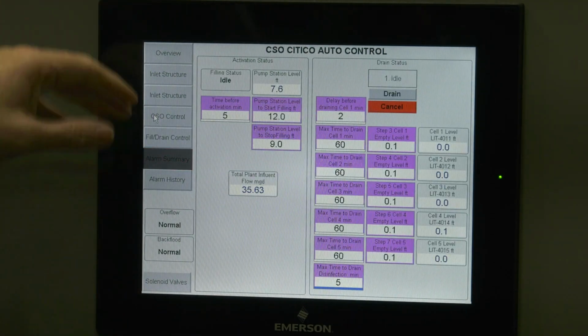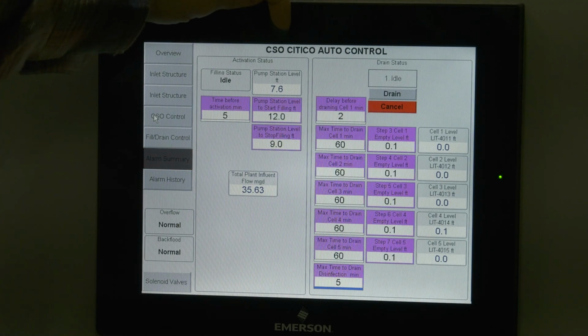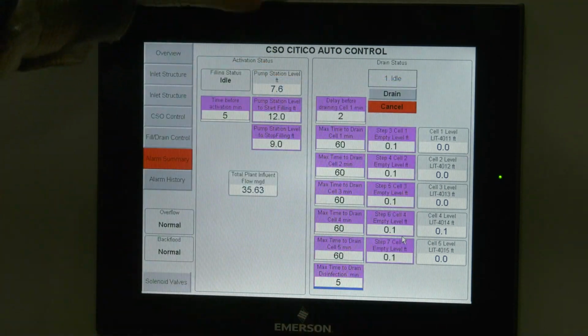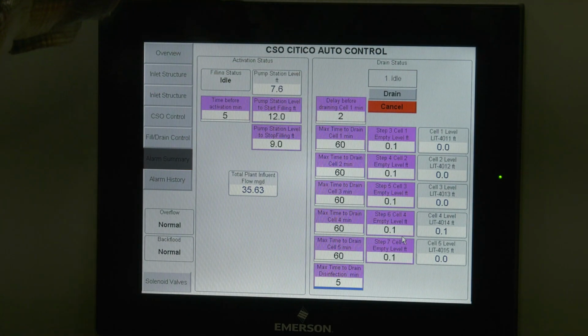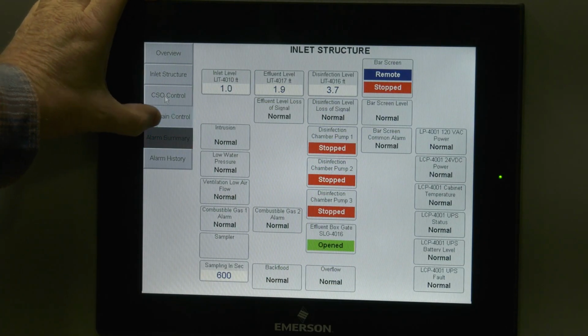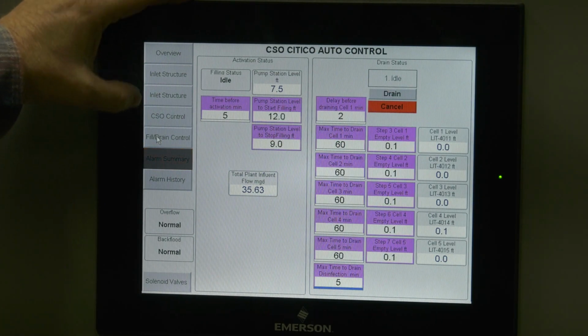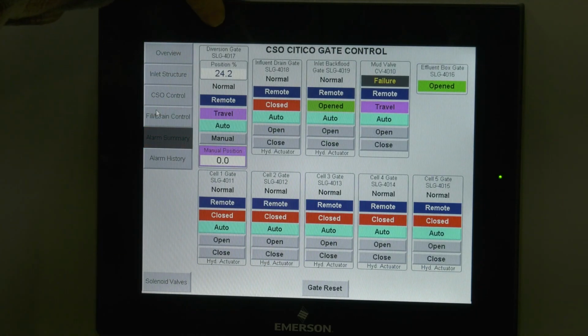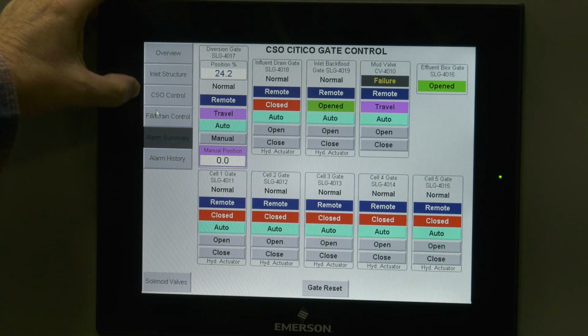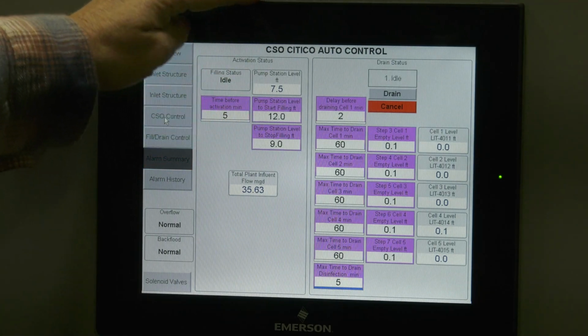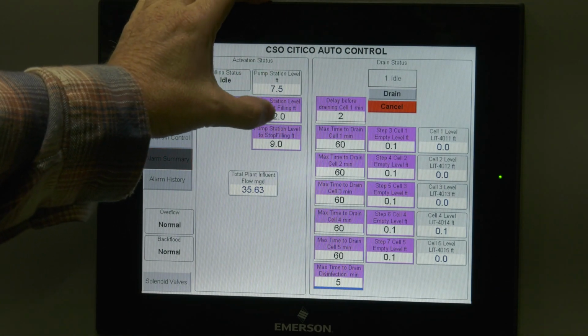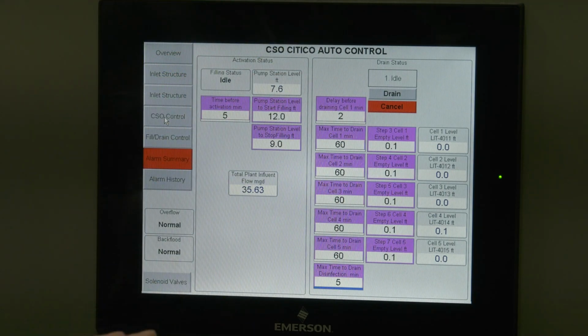CSO control. When the pump station level exceeds the operator adjustable set point for the start level, then it'll activate the filling mode, which will close the diversion gate SLG 4017. The inlet drain gate will stay closed, right? Okay. All right, and then the other gates, if they're not closed, will close automatically to fill. All right. Then, once we reach the pump station level stop filling, we just stop the filling sequence.